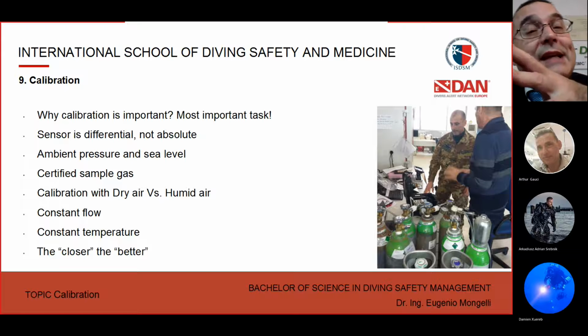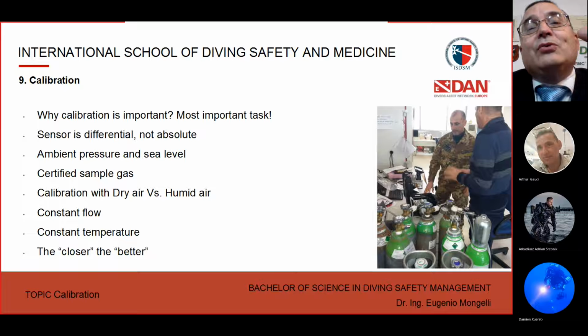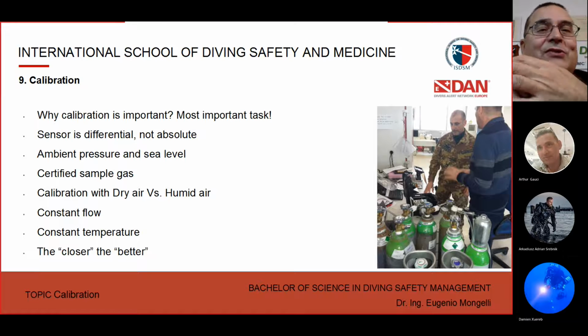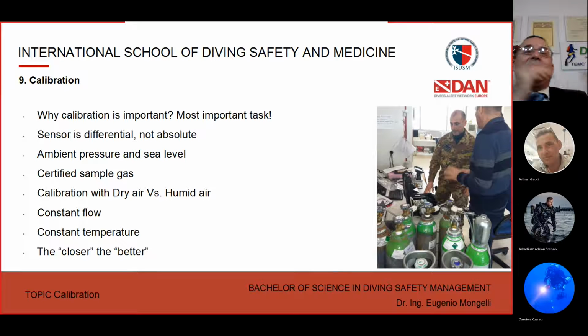So understand, if you are going to analyze a hyperbaric chamber in a saturation dive that is using 2% oxygen and 98% helium, the best possible gas for doing the calibration is not air, but 2% oxygen, 98% helium. If you do the calibration at this point, of course, you may have the best accuracy on the sensor. Okay, now you may say, okay, Eugenio, but we are not talking about the saturation dive, we are just talking about our diving center. Correct, but it's important that you know. Just for giving you an example, if you had to do analysis of 80% oxygen or 50% oxygen or 32% oxygen, which is the best calibration point?